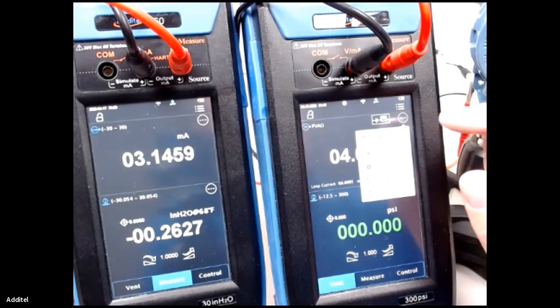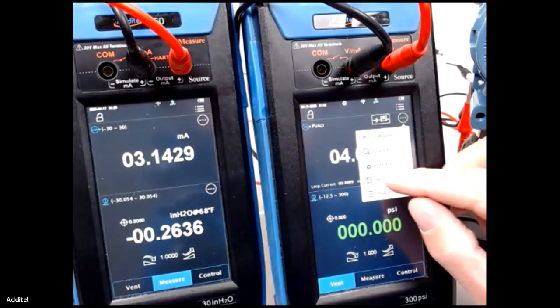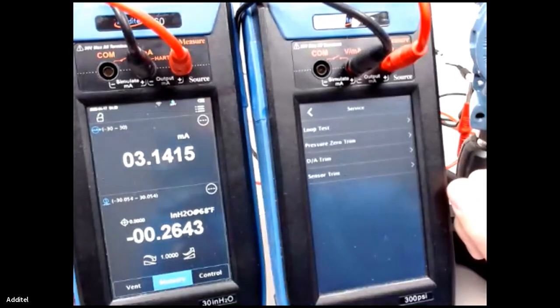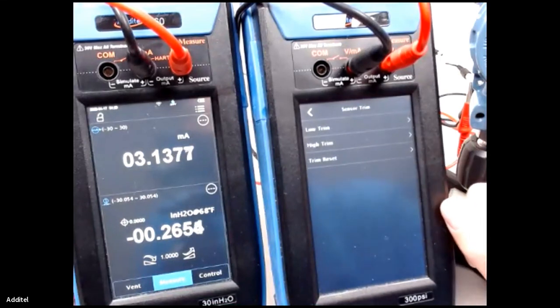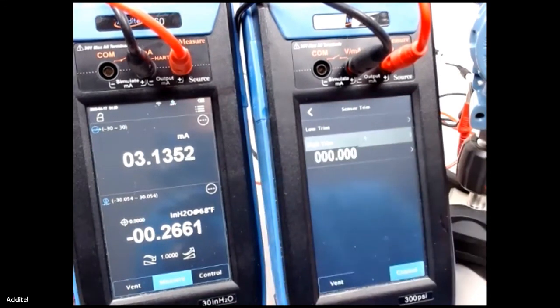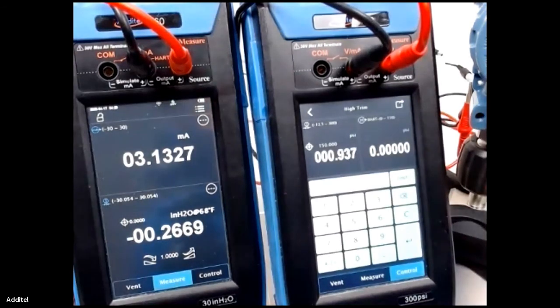So you can do that. Let's say we want to service this transmitter. Let's say we want to go and do a sensor trim. We want to set a high trim. The unit will literally go up to 150 PSI and it will stabilize out with the pump.